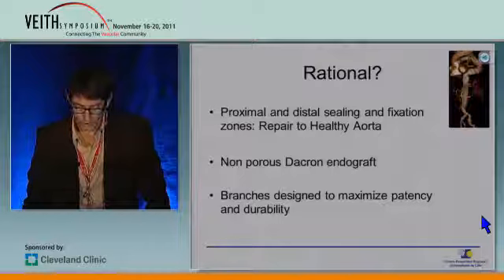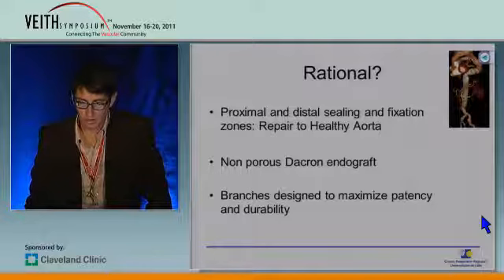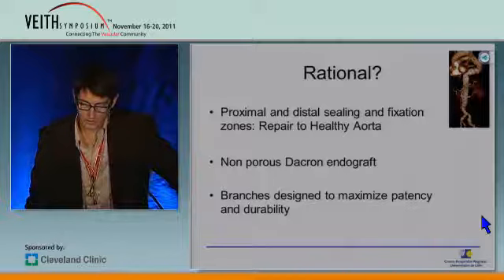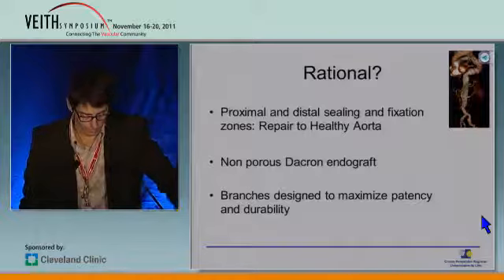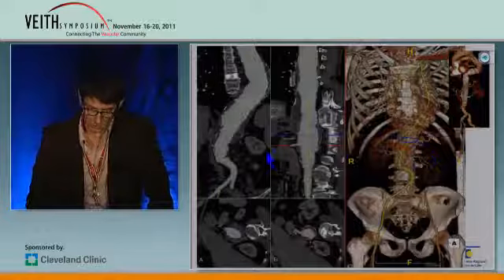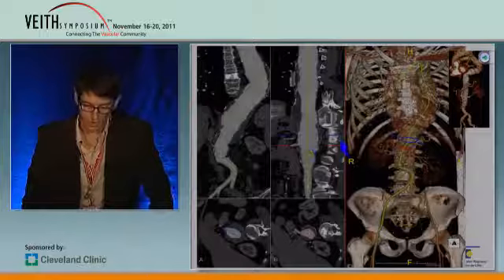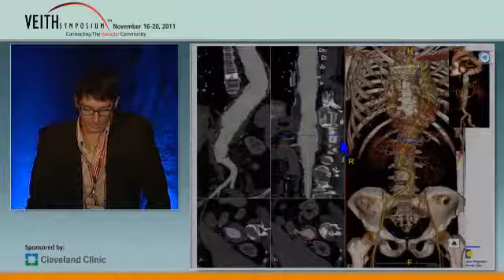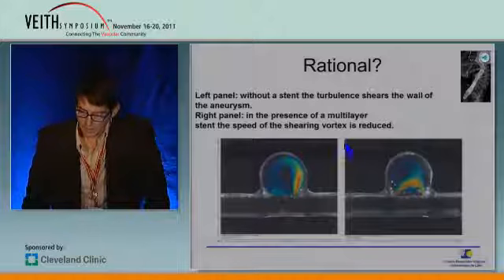So what's the rationale for using a branched endograft? You're going from proximal healthy aorta to distal healthy aorta — proximal to the aneurysm, distal to the aneurysm — implanting a non-porous endograft, and any visceral vessel in this area will be perfused by a branch of the endograft. We usually use 3D pre-reconstruction to depict the proximal and distal landing zone and to size our endograft. We've seen this morning that we have off-the-shelf options now, and we still have access to custom-made devices.